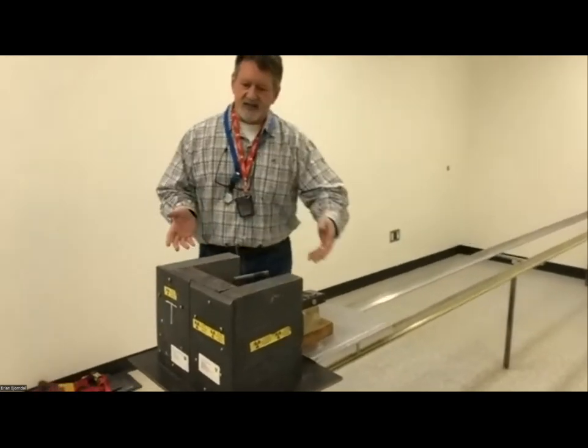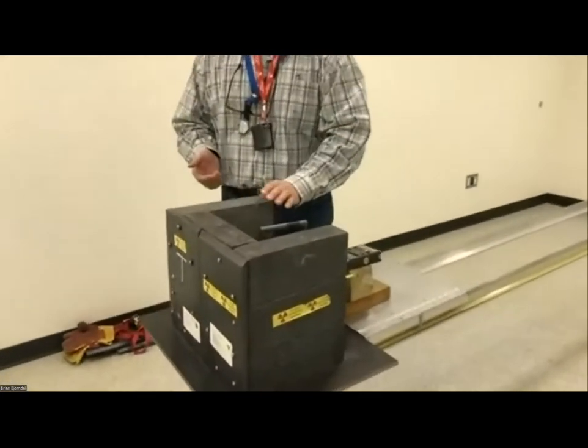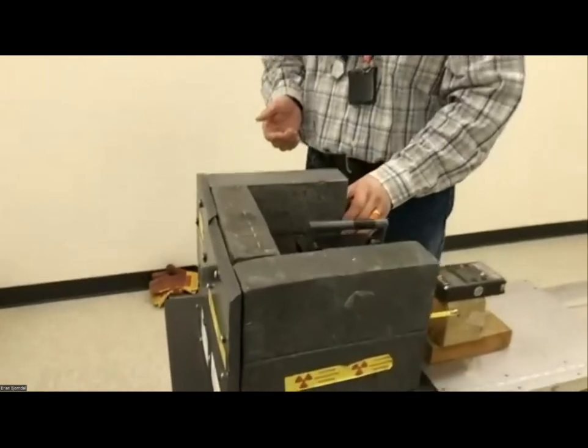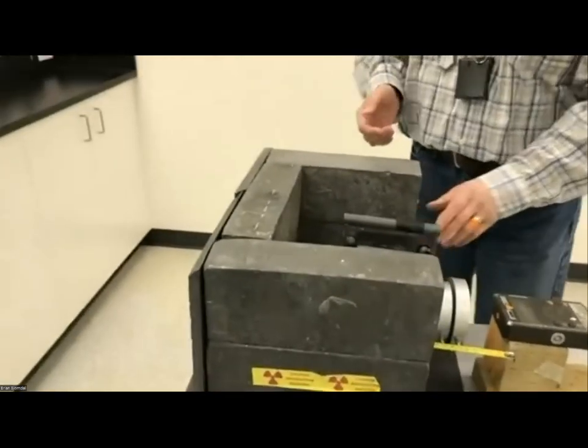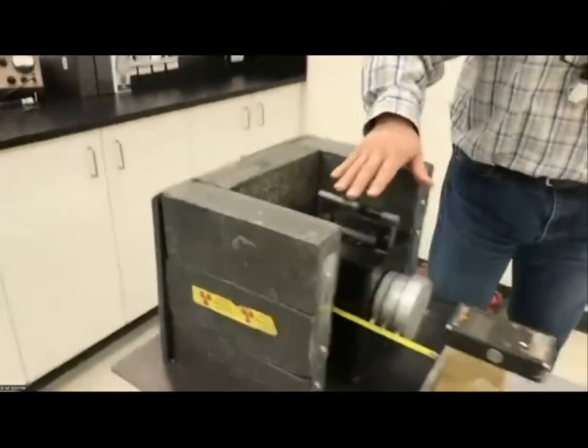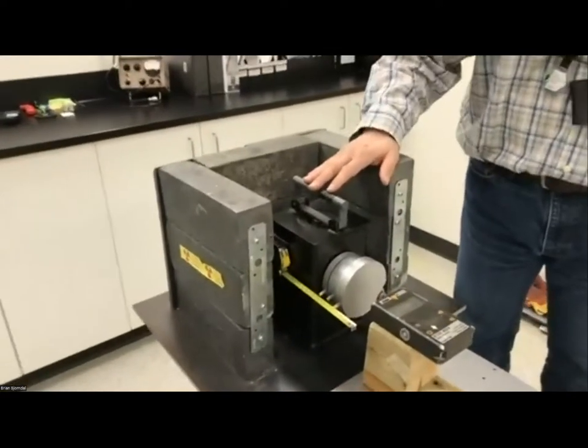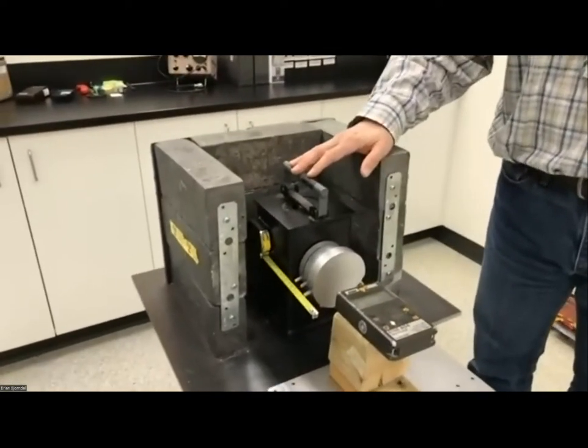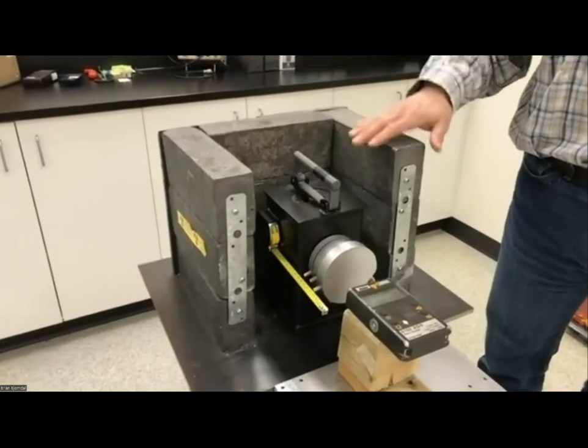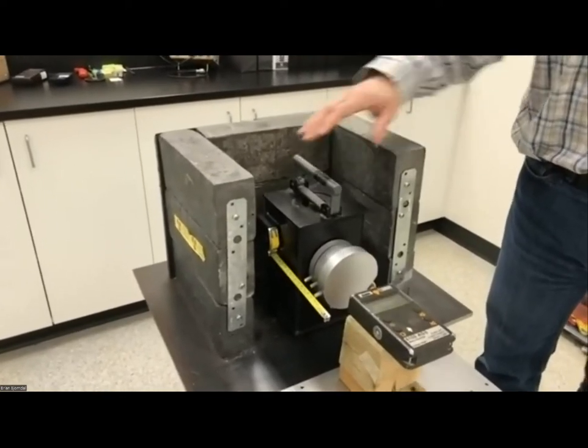You can see this device here is all shrouded in lead. These are lead blocks that we've manufactured around here to provide additional shielding. But you can see the device right here. Tell me if I'm going too fast, Tabby. This is a QSA model 773 cesium-137 instrument calibrator. So it's a commercial device.